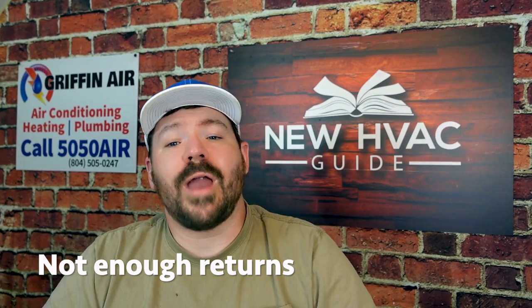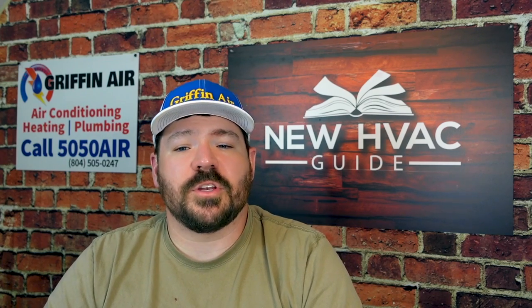Number six, not enough returns or not properly sized returns. And this probably goes for all ductwork, not just the return. I see systems all the time where the ductwork isn't sized correctly, or there isn't enough return air going through that system, and they're just asking for problems.